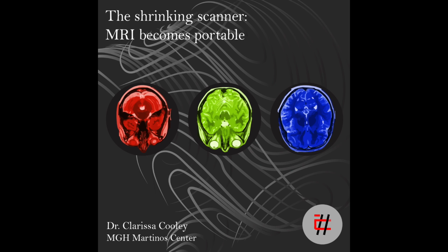And then the gradient coils tend to be quite heavy. They use big bundles of copper wire to produce these strong field gradients that are then switched on and off quickly using big power amplifiers. And those need water cooling systems. Traditionally, we want any field variation to be dominated by the field gradients for image encoding. This means that we need the B0 magnet to be really uniform or the gradients to be super strong. And both of these things contribute to the size, the weight and the cost of the system.